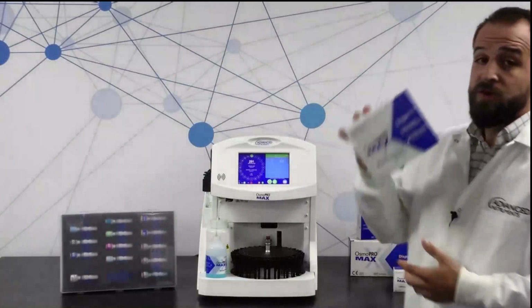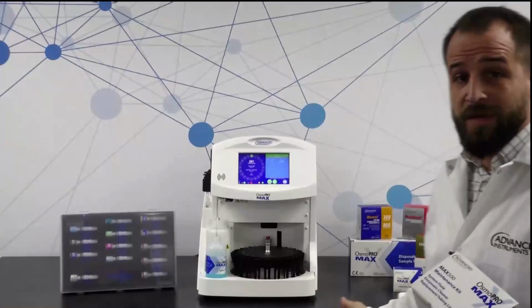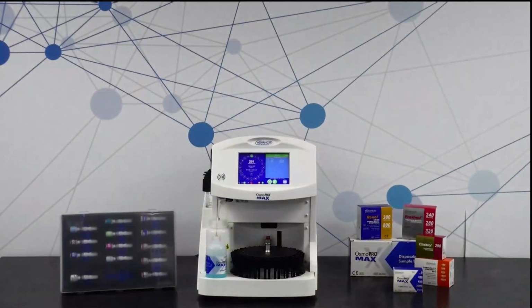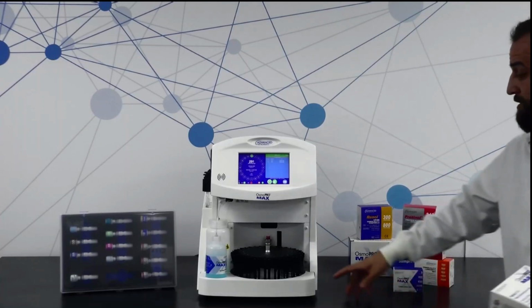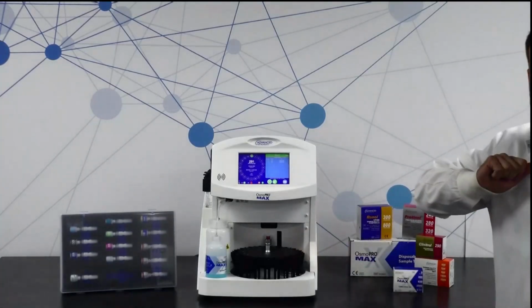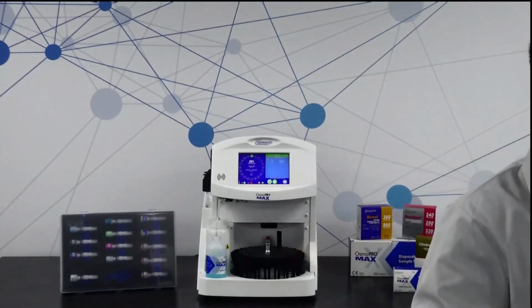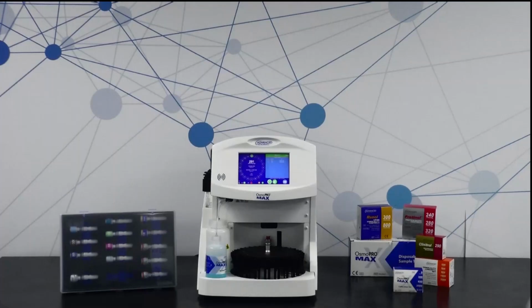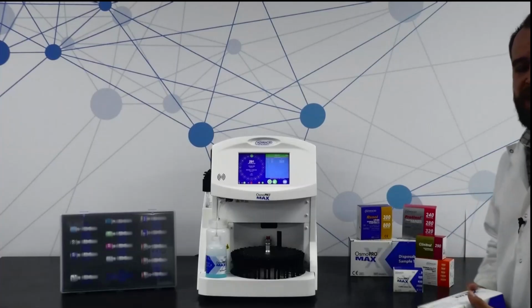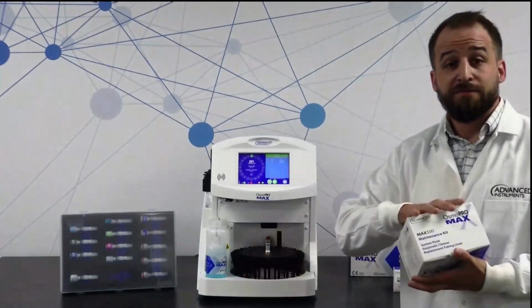But what's great about this kit, and what's great about this instrument, is you can continuously test from primary sample tubes. Any of those tubes that you typically get sent up to the laboratory for serum and plasma—lithium heparin tubes, gel separator tubes, red tops, SSTs, whatever you get—it's going to fit on this turntable as long as it's shorter than 100 millimeters tall. And it is going to allow you to put those tubes on and take them off as they complete testing. You can continuously do that, no batch testing. You can keep putting tubes on and taking them off until you hit 500 tests.